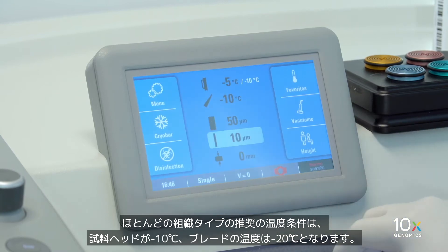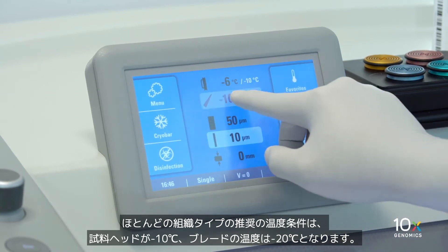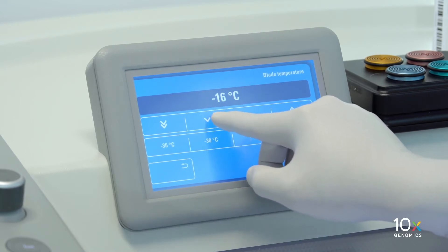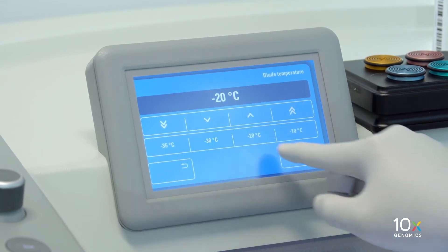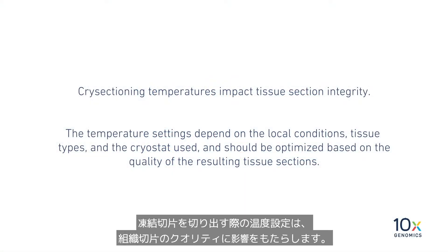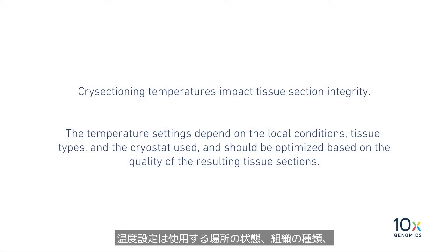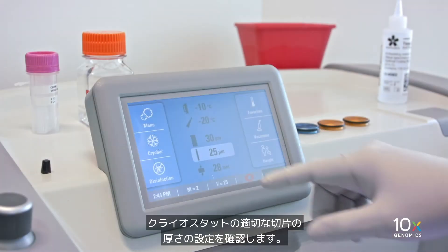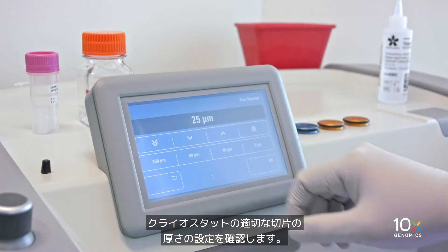The recommended sectioning temperatures for most tissue types is minus 10 degrees Celsius for the specimen head and minus 20 degrees Celsius for the blade temperature. Cryo sectioning temperatures impact tissue section integrity. The temperature settings depend on local conditions, tissue types, and the cryostat used, and should be optimized based on the quality of resulting tissue sections.